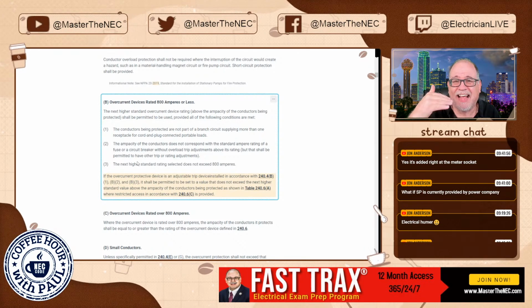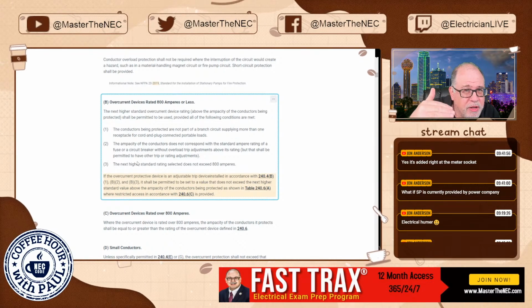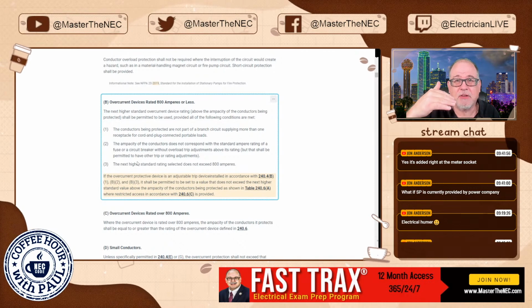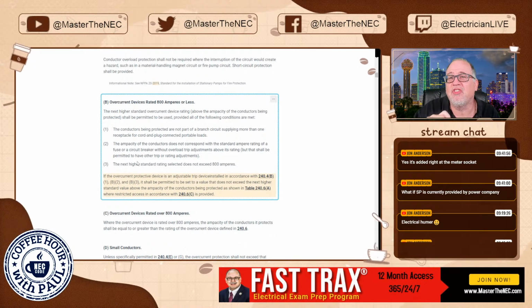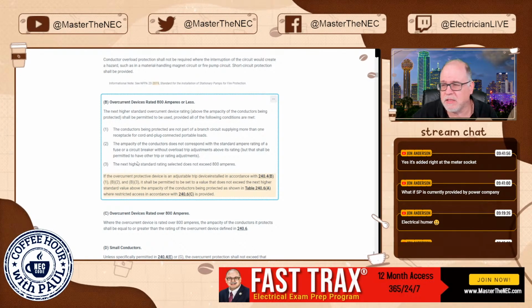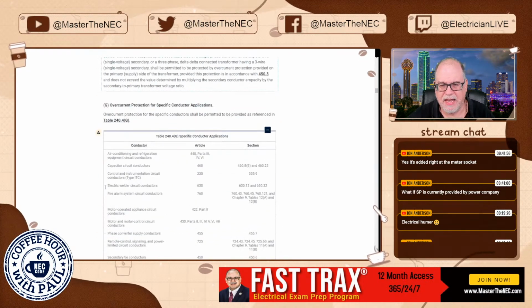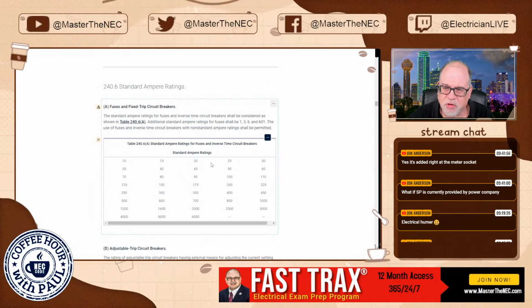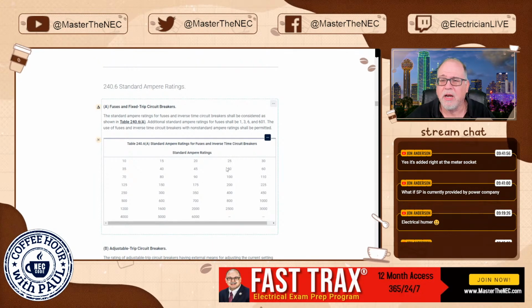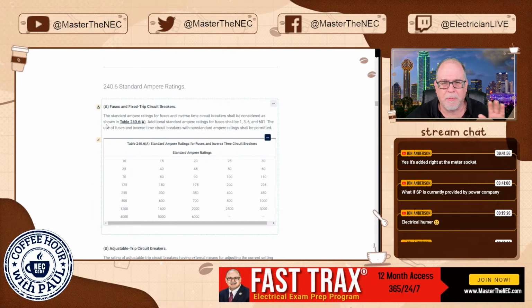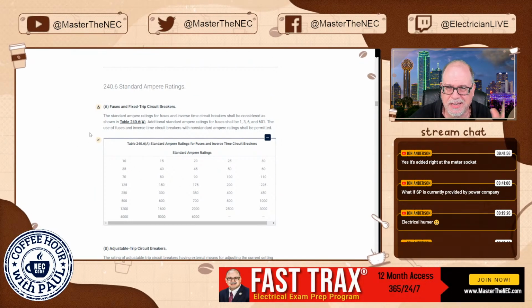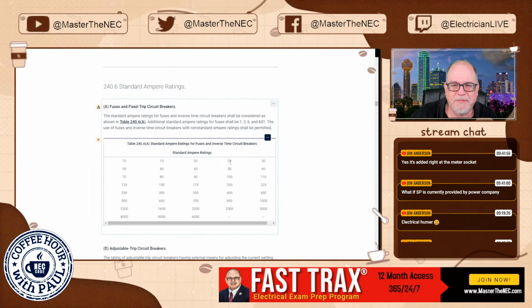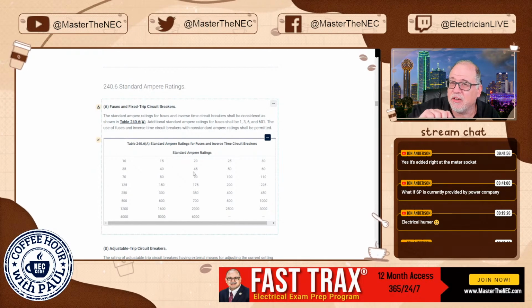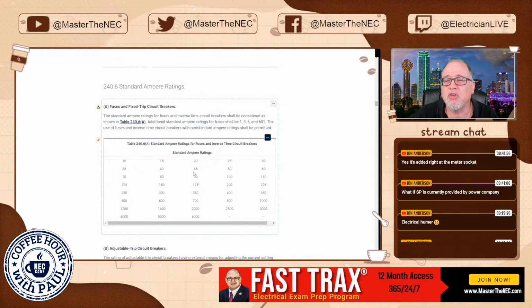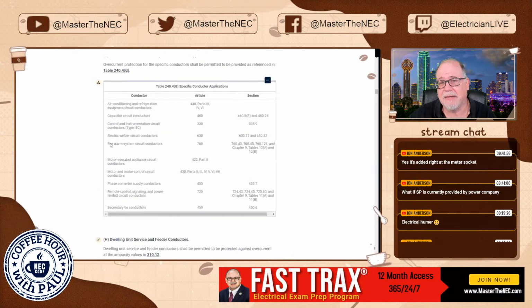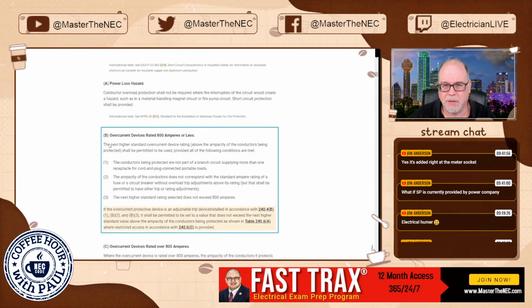But if the next size was, say, a 25 amp standard circuit breaker that's listed in 240.6(A), then I would be able to adjust it up to that value, okay? So if it was 23 amps, let's say, and I have to go look here. I don't have anything for 23 amps. So the next size up allows me to go, I'm just throwing numbers out here, up to 25. Now again, I don't want to hear anybody say anything out here about small conductor rules. I'm just explaining what we mean by the adjustable trip. Okay, 23, it doesn't correspond, I go to 25. Now, if I have an adjustable, then I could adjust it up to 25 and still utilize that adjustable trip. So that's huge for folks that use that. Okay, so that's what we're talking about.